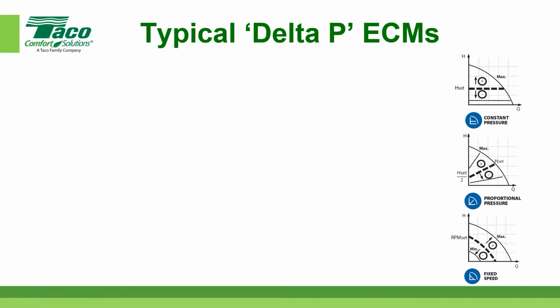It's pretty simple. You say, well, how accurate is it? Engineering has told us it's within 5%. So 95% accurate. And that's as good as circuit balancing valves or those little sight flow indicator balancing devices. Caleffi's got some nice ones. Ours, you push in, and there's your pull out. There's some good equipment out there, but the accuracy on those is about the same as the reading of these high efficiency circulators. Anyway, let's get into this.